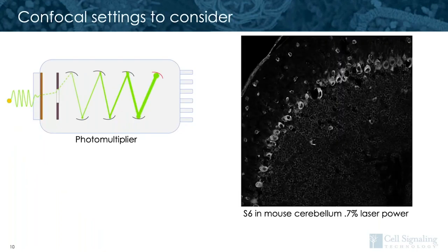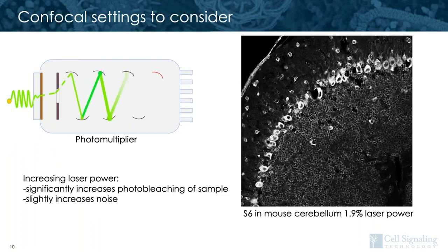On the confocal, there are a few ways to manage signal. First would be to increase laser power. By increasing the power of the laser, you're increasing the number of photons that excite your sample, as well as the number of photons that are emitted and detected by the PMT. However, the more energy your sample is exposed to, the more photobleaching of your fluorophores will occur. Furthermore, increased laser power will also slightly increase the noise in your image.